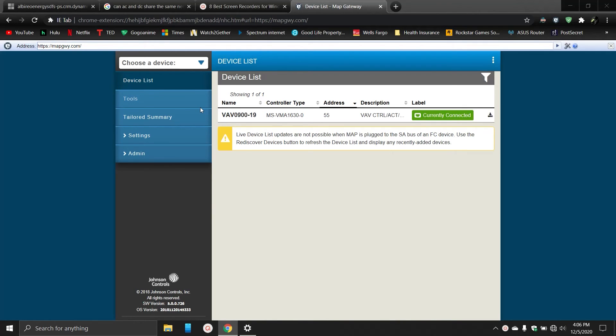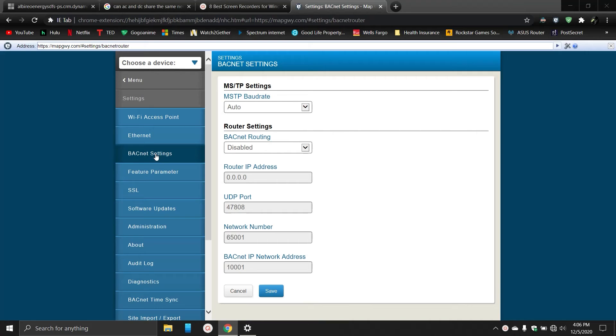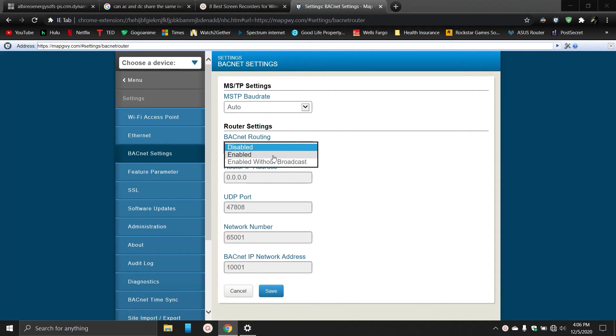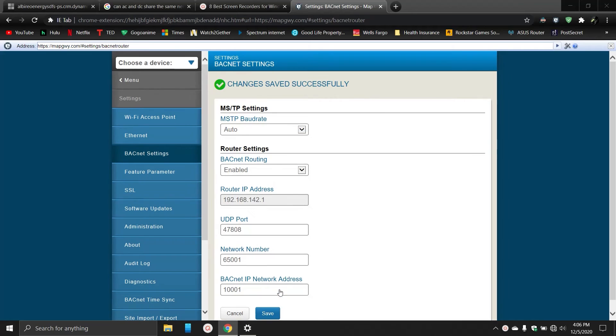What you want to do is actually go to settings, then BACnet settings, and this BACnet routing you want to turn on enable. If you don't turn that on we can't actually scan the network from the SA bus. So once that's enabled, click save. Changes saved successfully.